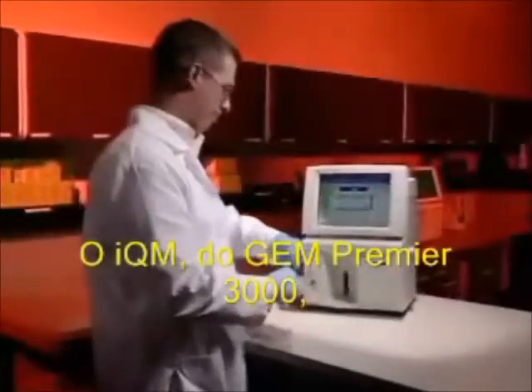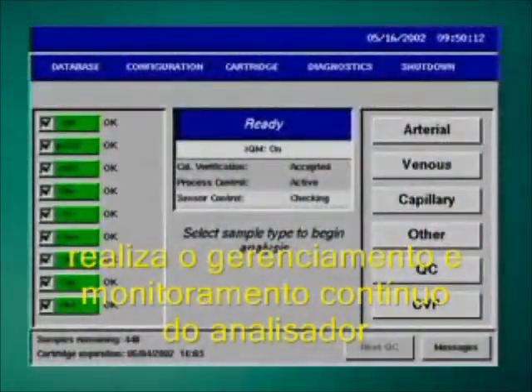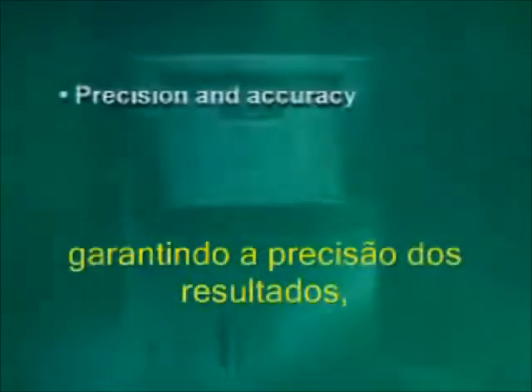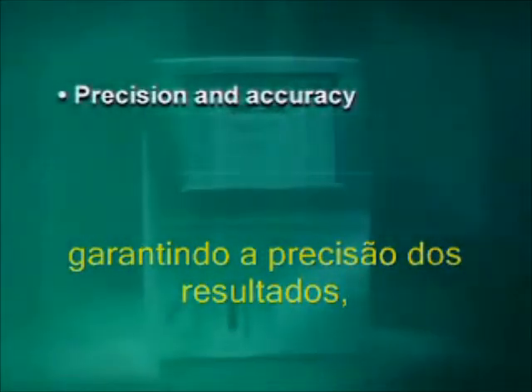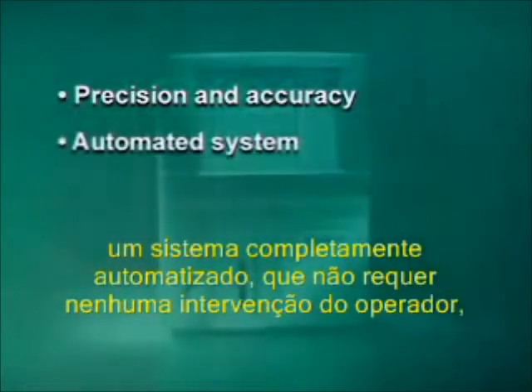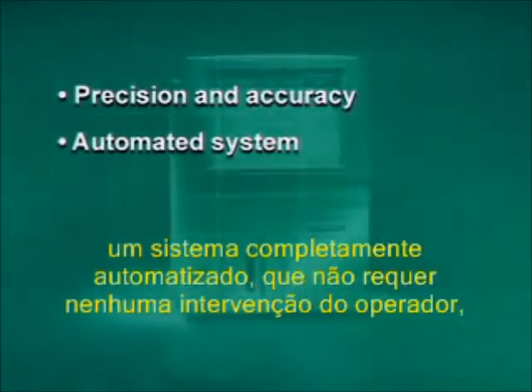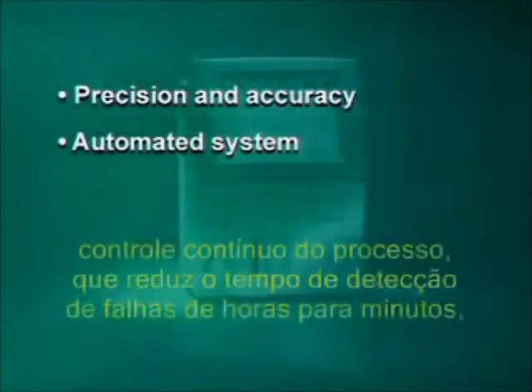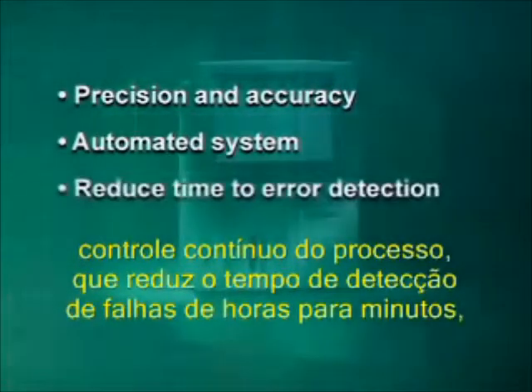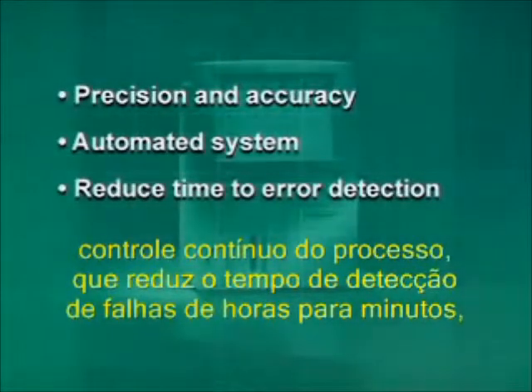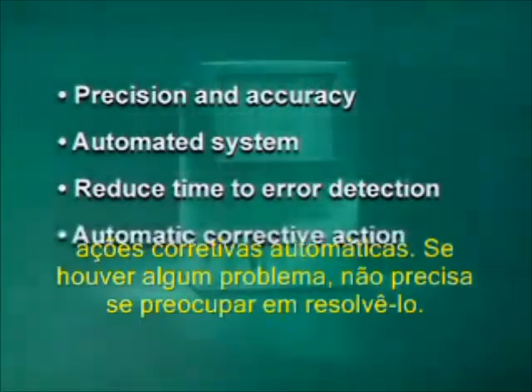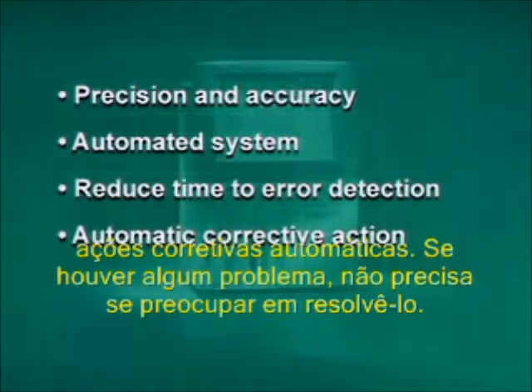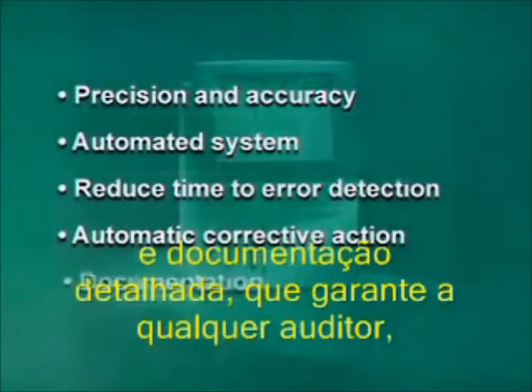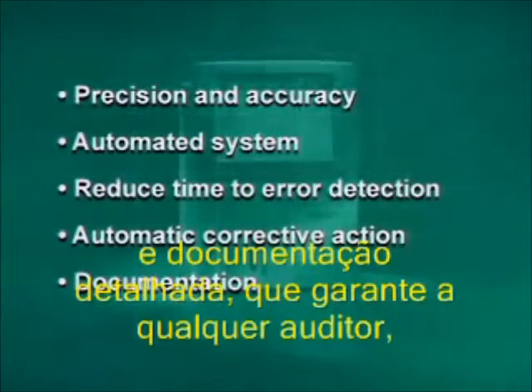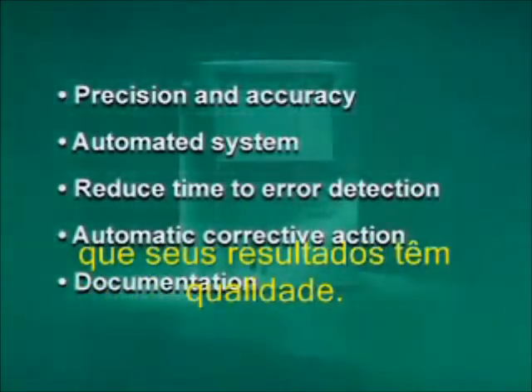With the GEM Premier 3000 Intelligent Quality Management System, you get active management and monitoring of the analyzer's performance, ensuring precision and accuracy of test results. A completely automated system with no human intervention or time-consuming external QC required. Continuous total process control to reduce time to error detection from hours to minutes. Automatic corrective action, so if there is a problem, you don't have to worry about fixing it. And detailed documentation that assures regulatory inspectors that you are delivering quality results.